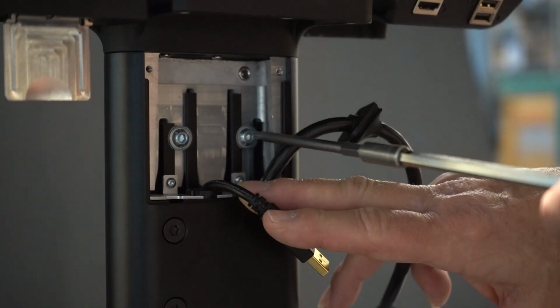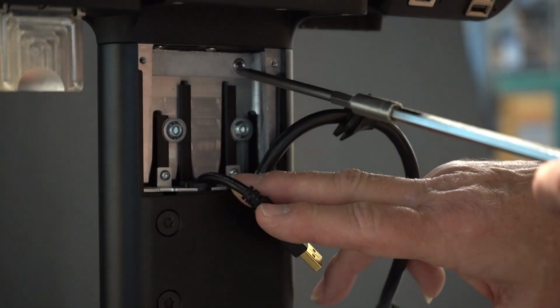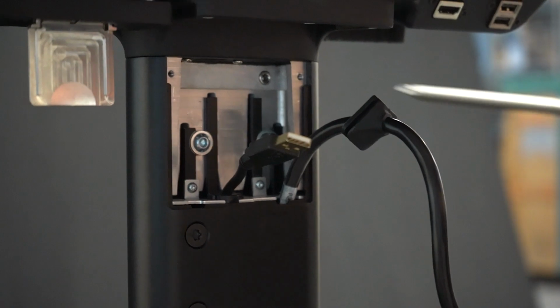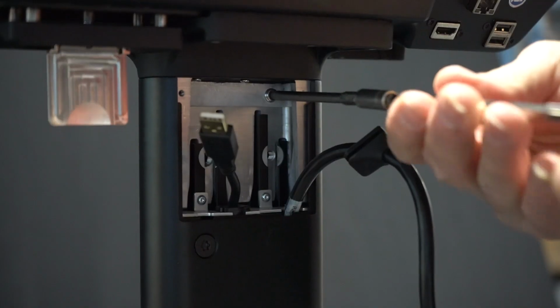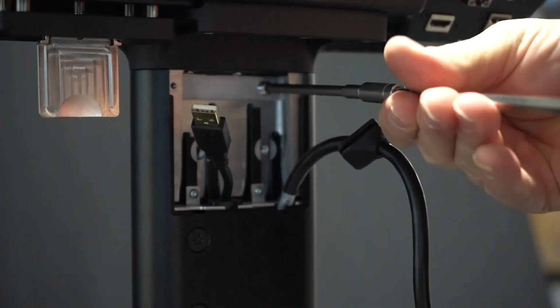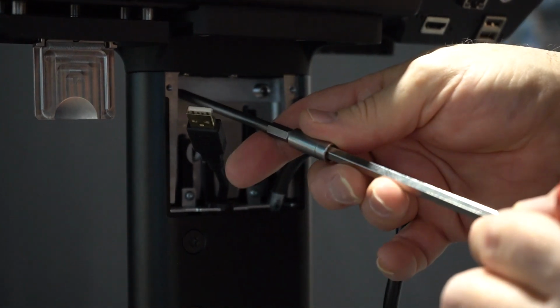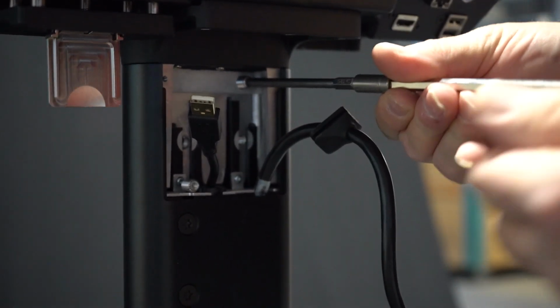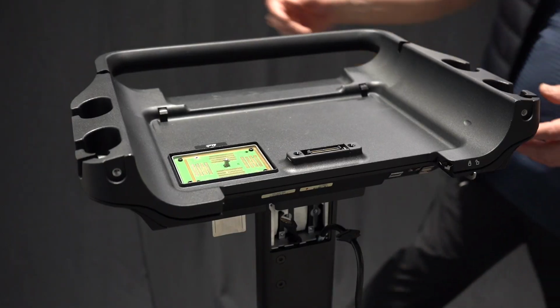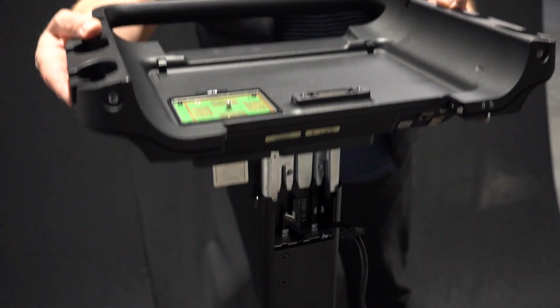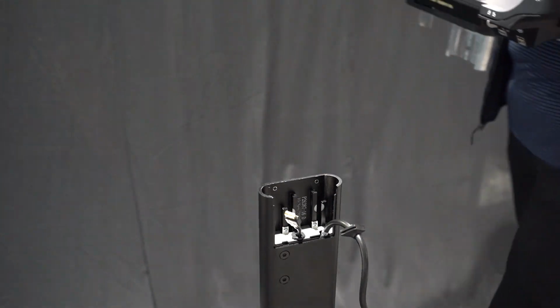Use the magnetic bit driver and the 4mm hex head bit to remove the 2 M4 by 20mm screws securing the stand head to the stand. Use the magnetic bit driver and the 4mm bit to loosen the 2 set screws securing the stand head to the stand. Remove the stand head from the inner stand column by lifting the stand head pedestal up.